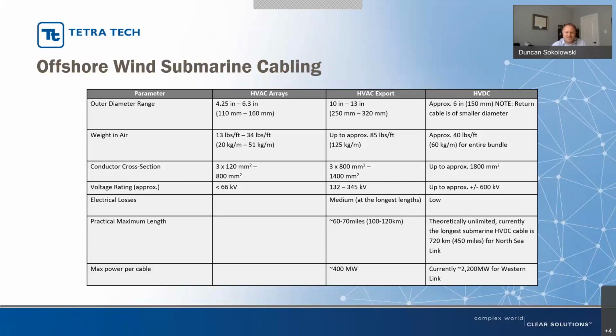Practical maximum distance varies a little, but it's in the order of 60 to 70 miles for AC cables. And as a rule of thumb, a single HVAC cable can transmit about 400 megawatts of power, so an 800 megawatt wind farm would generally require two export cables.